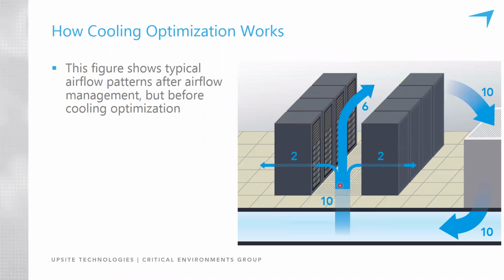But we still have 6 units of bypass airflow because the IT equipment only requires a total of 4, leaving 6 units of conditioned air to leave the cold aisle. And this air will leave the cold aisle whether it has doors or a roof or baffles or not. This extra air will leave. If it's just baffles and a partial containment, then that 6 units will leave out the top of the aisle. If it's full containment with full doors and a full roof, then that extra 6 units of air that's not needed by the IT equipment is going to be forced through the IT equipment. Also wasted, same amount of waste.